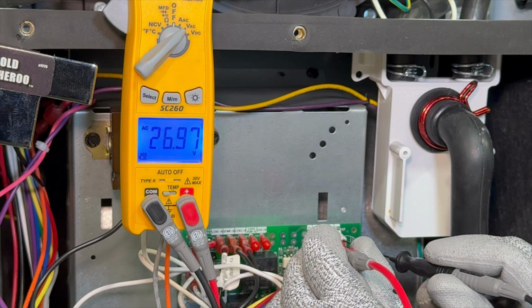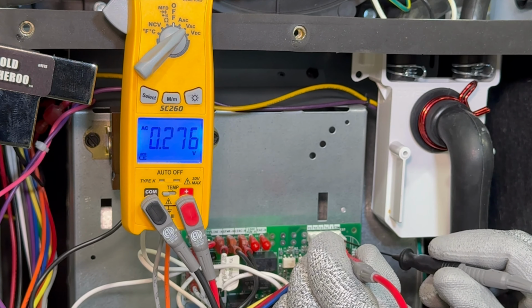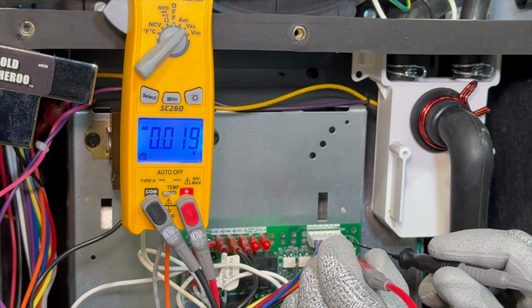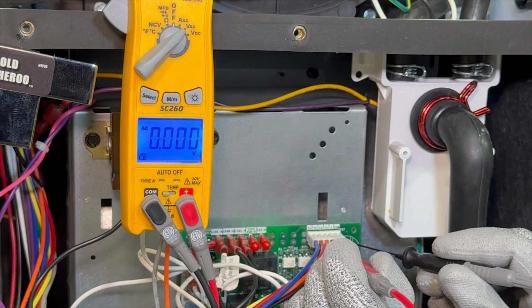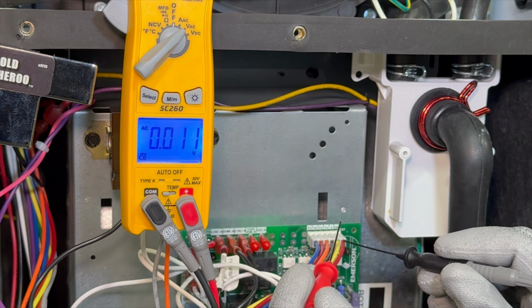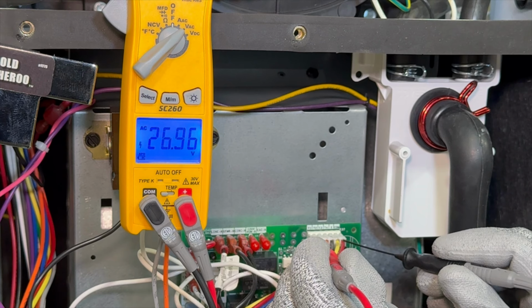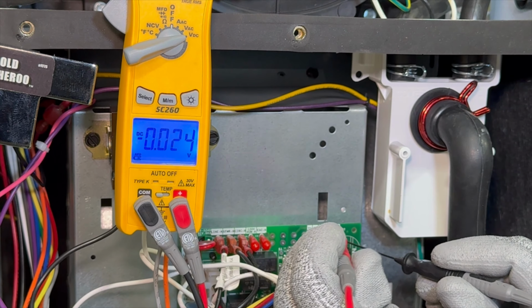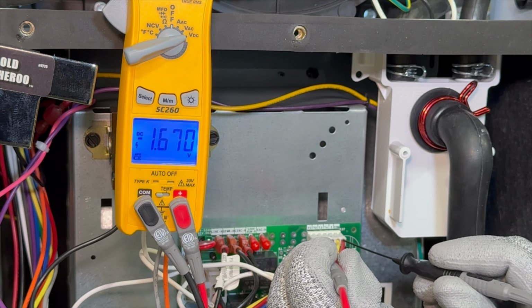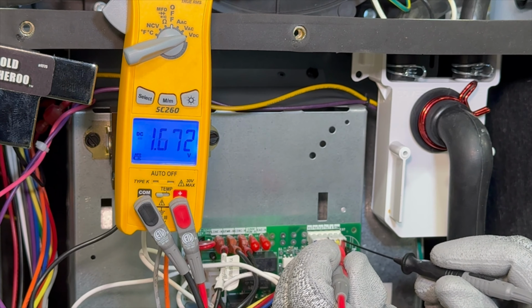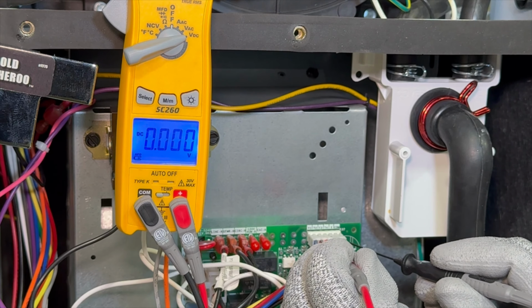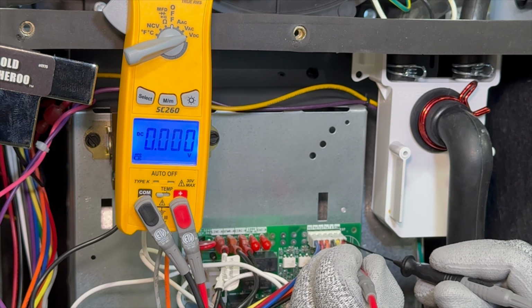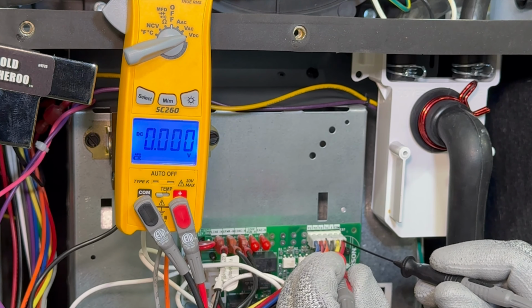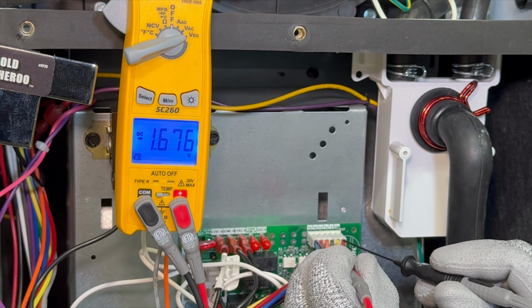Now we have 24 volts AC versus the DC voltage that we previously had. So we're just going to run through the pins, double check that we don't have any other voltages being applied to our motor speed taps, and we'll go ahead and put our meter on volts DC just to check, but we positively have a 24 volt AC signal on this particular board. If we were to check from common to that same T1, we might see a little residual voltage in there, but our actual ECM fan speed tap voltage is 24 volts AC. So even though we have the same 6-pin connector on both furnaces, one is using a 24 volt AC signal, one is using approximately 8 volts DC.